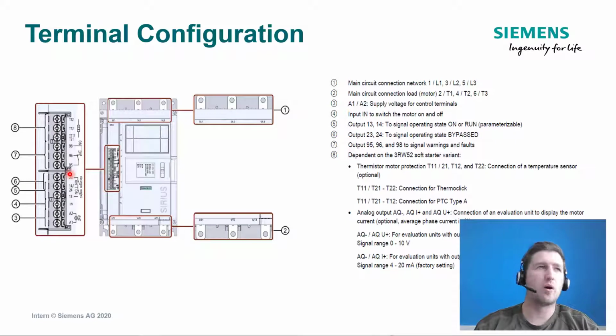mode. So what do we mean by bypass mode? Bypass mode is when you've reached the full line voltage, the thyristors have finished switching, and then the device switches over to the mechanical bypass contact, hence bypassed. So this next terminal here, number 4, is the in signal. And this next contact here is the control voltage A1 and A2. So for the soft starter to actually start, you need to have a signal going to in, and you also have to have a control voltage. So without those two functions, you don't have a start.